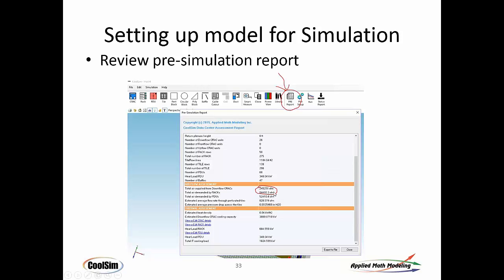You see it comes up and it shows you a couple of things. The one that I always look at right away is the ratio of airflow coming from the cooling unit to airflow demanded by the racks. This is sometimes referred to, if any of you have been to DCEP training, as the RTI ratio. And you want it to be fairly close to 1, but you don't want it to be way off. If you notice, I pulled this one on purpose because you can see here there's quite a difference. The cooling units are supplying 245,000 CFM in this case, and the racks only need 84,000.